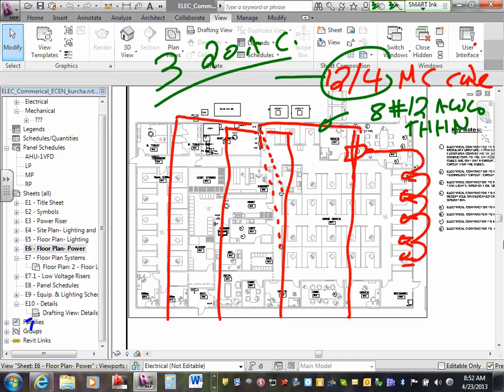That's not a realistic way to do it. You're not going to have 3 circuits worth of power on one 3-pole breaker at the panel. You're not going to pull a multi-wire, you're going to pull 12-2. Why not? Unless the engineer tells you not to pull it, why not? Because it's not common, you don't do it anymore. It's bad wiring practice for a building, and from a maintenance standpoint, you're just not going to see it.